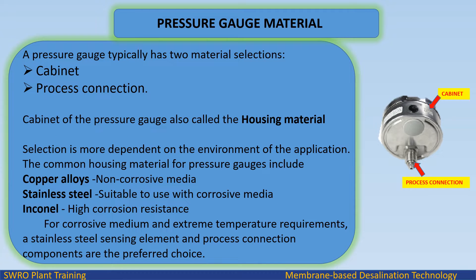Pressure gauge material: A pressure gauge typically has two material selections — cabinet and process connection. The cabinet, also called the housing material, is selected based on the environment of the application. Common housing materials include copper alloys for non-corrosive media, stainless steel for corrosive media, and Inconel for high corrosion resistance. For corrosive media and extreme temperature requirements, stainless steel sensing elements and process connection components are the preferred choice.